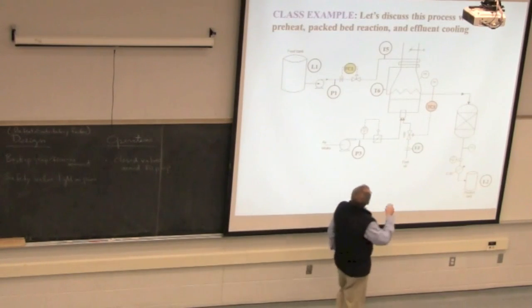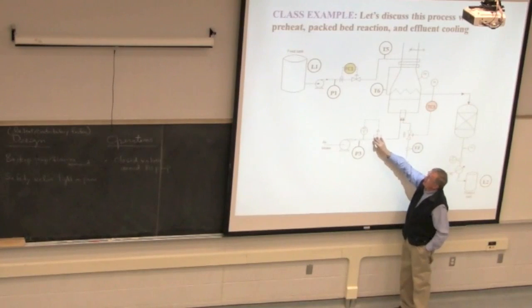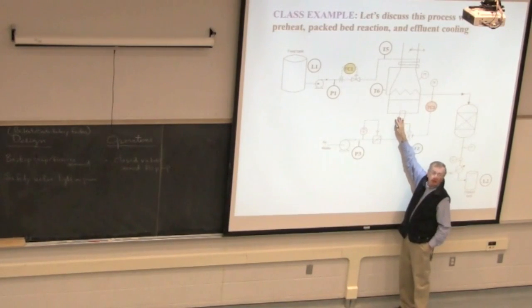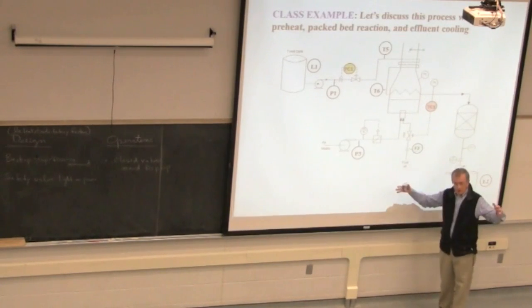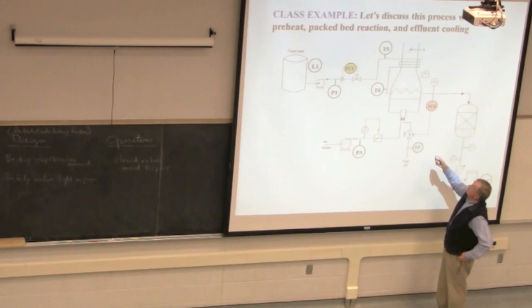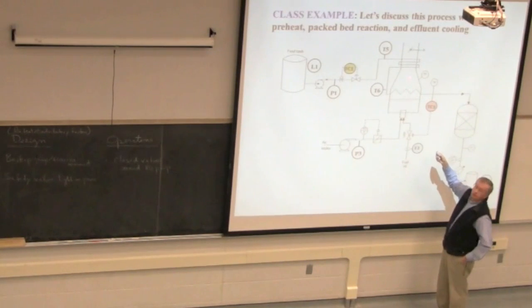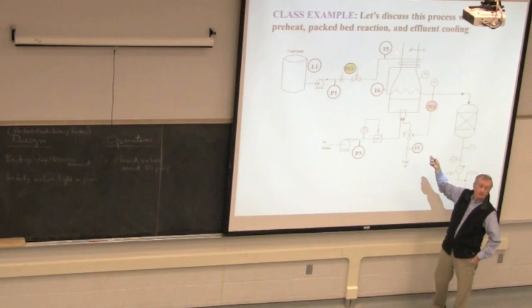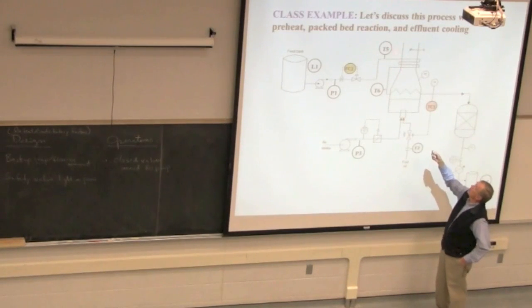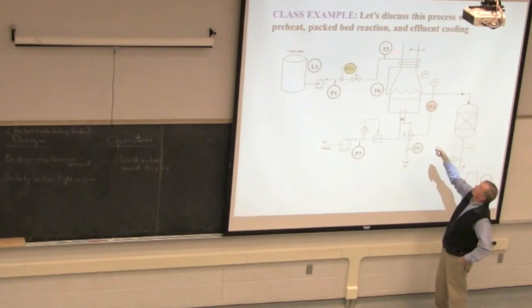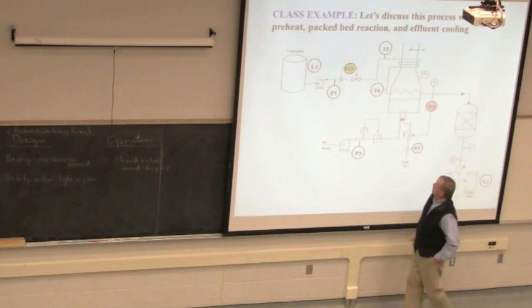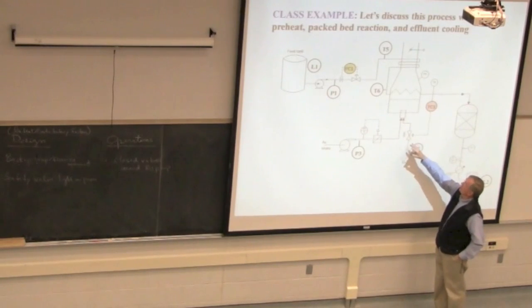Okay, so the fired heater, there's a flame here, so we're mixing air and fuel. Could be lots of burners, could be a single individual burner. It could be on the floor, or on the walls, all kinds of different designs. So there's radiation and convective heat transfer here, and then as the flue gas leaves, it's still hot. So we have some extra heat exchange up here, which has no radiation, just convection. You can think of this as a pre-heat exchanger, and then the second heat exchange here.